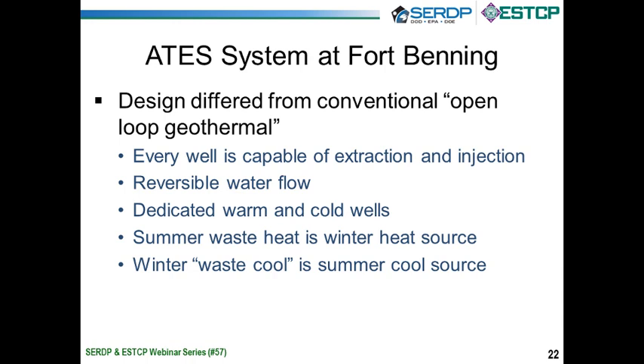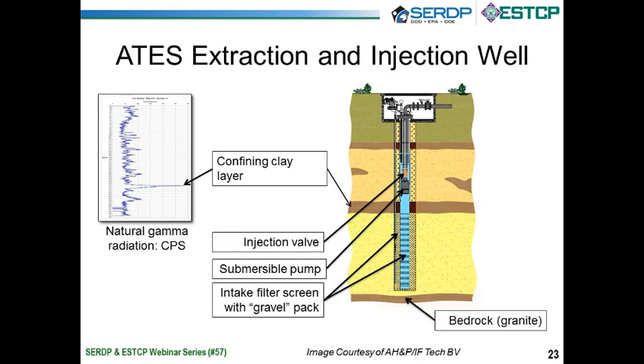But if you did have movement, you'd see this blue wave and red wave and blue wave and red wave heading downstream, and you throw it away. That's the way open-loop geo is typically designed when it's not ATES. It works great because the water is much cooler or warmer than the air at the appropriate time, but you don't capture the waste heat at all. ATES allows us to capture the waste heat and back flush the wells periodically. Inherently, it is reversible. This is kind of an illustration. It's not perfect, but it's close to what's going on here.